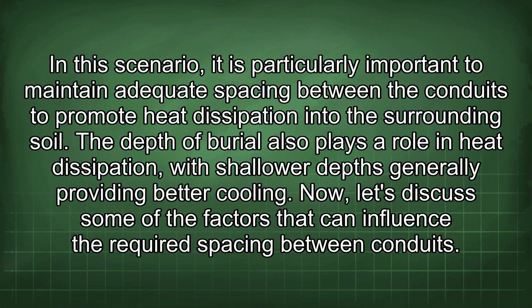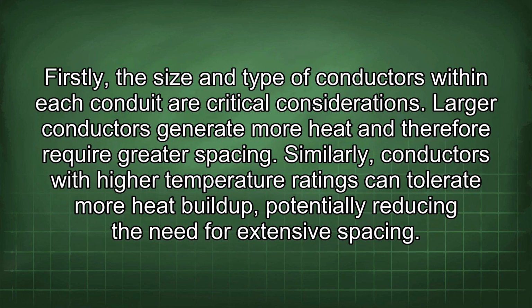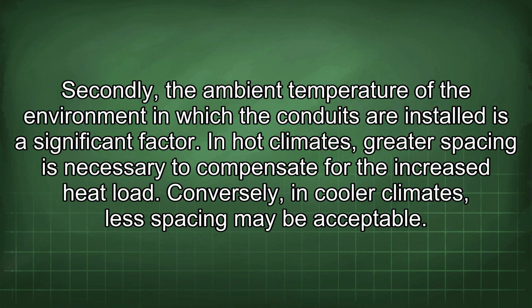Now, let's discuss some of the factors that can influence the required spacing between conduits. Firstly, the size and type of conductors within each conduit are critical considerations. Larger conductors generate more heat and therefore require greater spacing. Similarly, conductors with higher temperature ratings can tolerate more heat buildup, potentially reducing the need for extensive spacing. Secondly, the ambient temperature of the environment in which the conduits are installed is a significant factor. In hot climates, greater spacing is necessary to compensate for the increased heat load. Conversely, in cooler climates, less spacing may be acceptable.